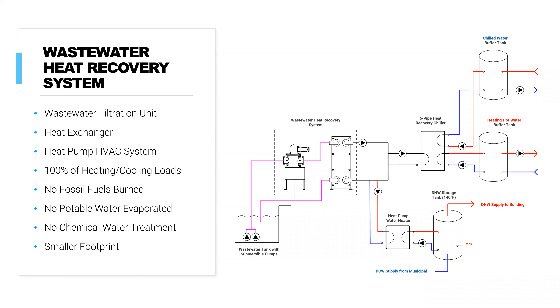So the HVAC equipment actually used in the building, one of them was known as a heat recovery chiller. You'll see there it's got 6 different pipes. One set of pipes is for what is known as the source, which in this case would be the wastewater energy recovery system. One is the hot water loop, and the other is the chilled water loop. Those hot water and chilled water loops are supplying what's next to it, which is known as a chilled beam. So don't let the name fool you. It says chilled, but it can also provide heating.